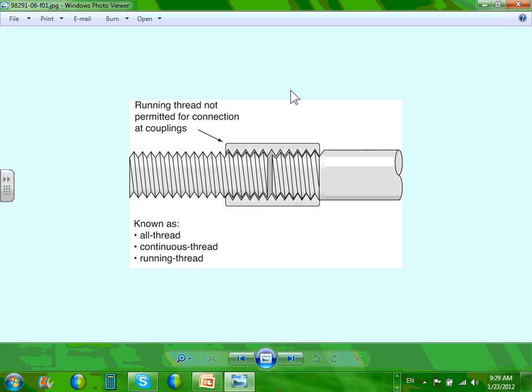The problem with running threads, as they call them: you can move this one all the way up, all the way this way, all the way up. The challenge with this one is that it doesn't give you a good equipment grounded conductor connection. That's the disadvantage of it, so be aware of this. Running threads are not permitted for connection at couplings because they don't give you a good equipment grounded conductor. I don't like to emphasize that one because it's for electricians.